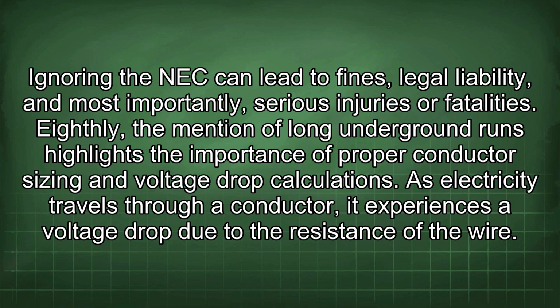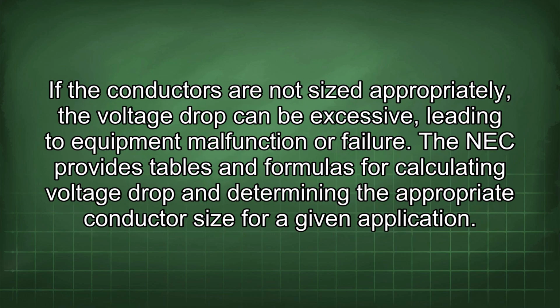Eighthly, the mention of long underground runs highlights the importance of proper conductor sizing and voltage drop calculations. As electricity travels through a conductor, it experiences a voltage drop due to the resistance of the wire. If the conductors are not sized appropriately, the voltage drop can be excessive, leading to equipment malfunction or failure. The NEC provides tables and formulas for calculating voltage drop and determining the appropriate conductor size for a given application.